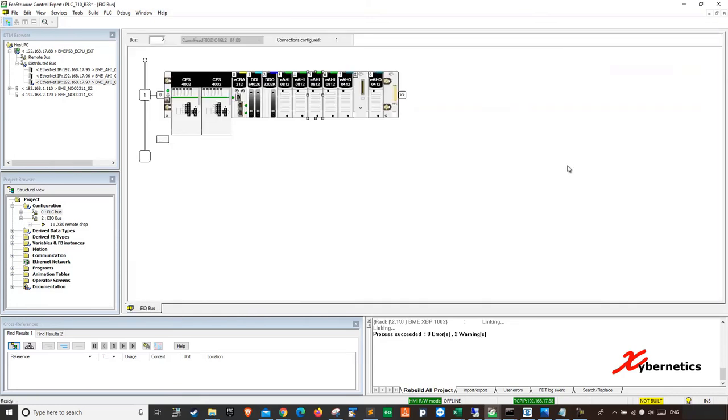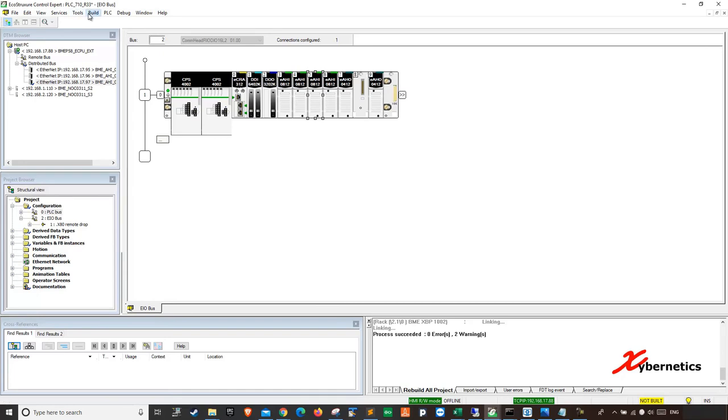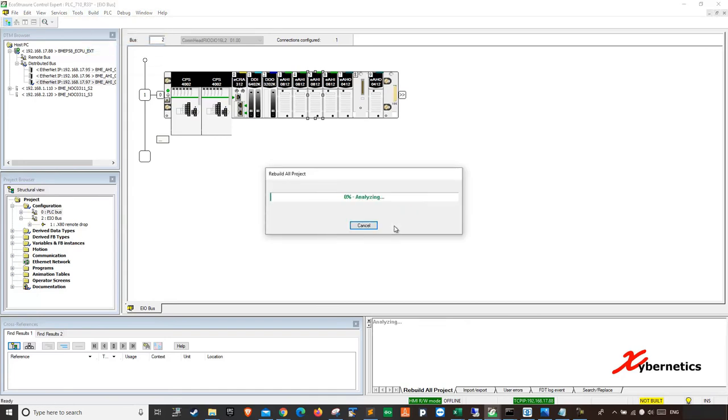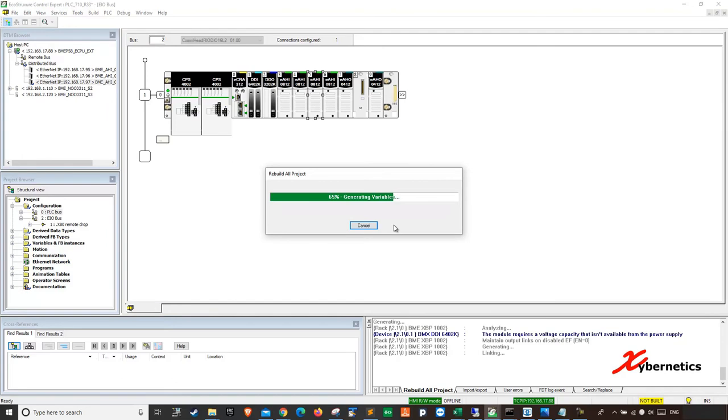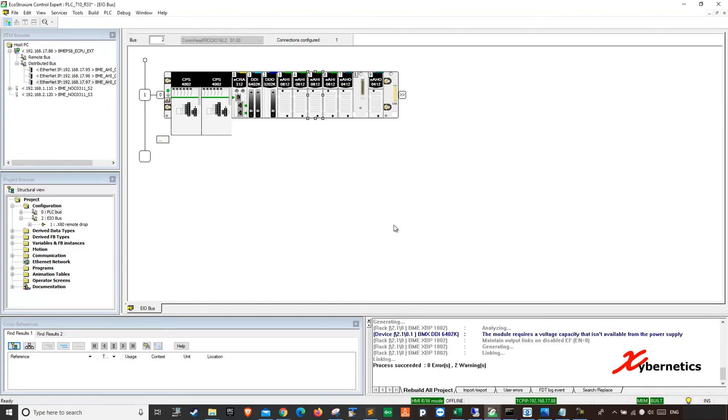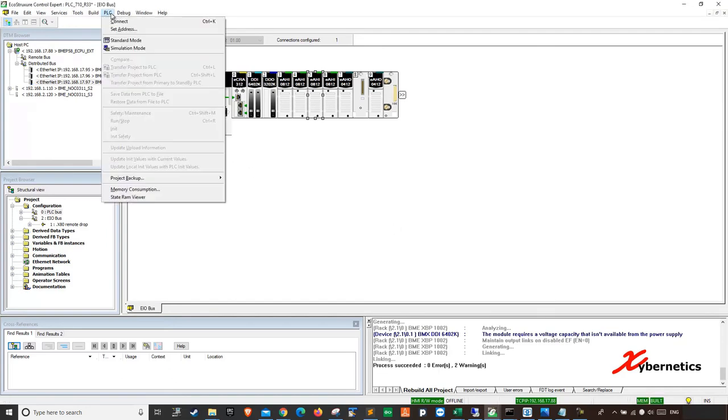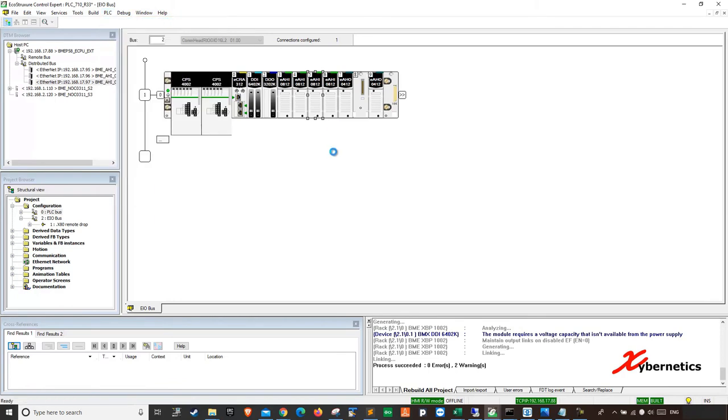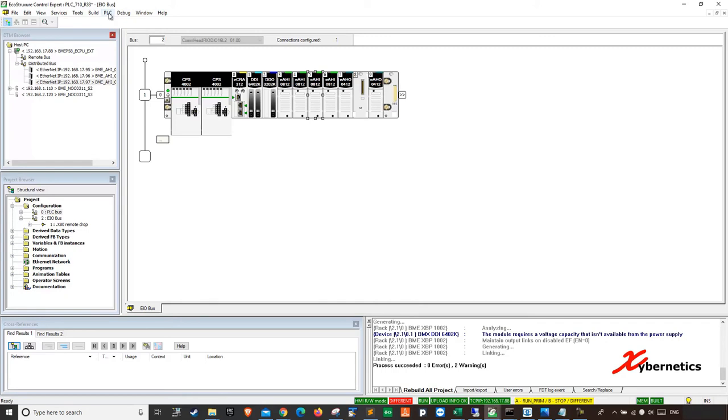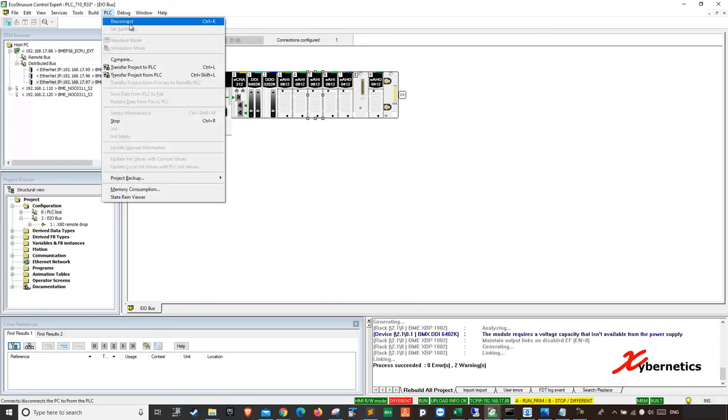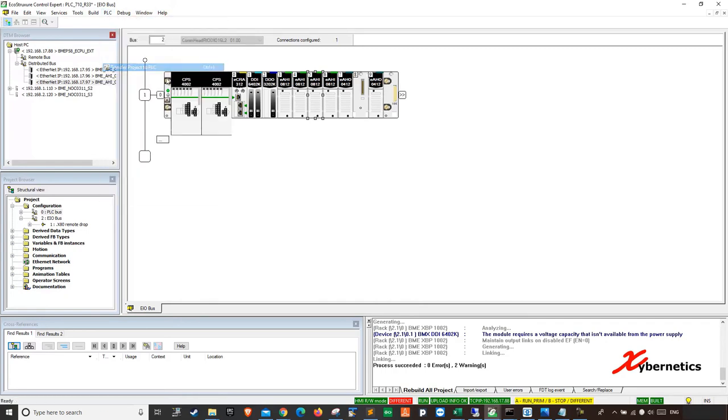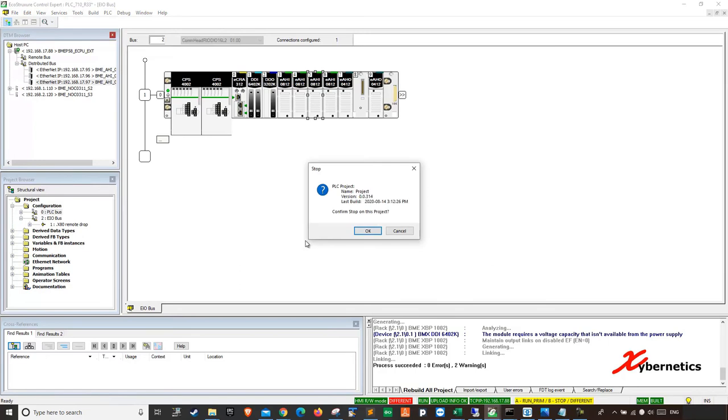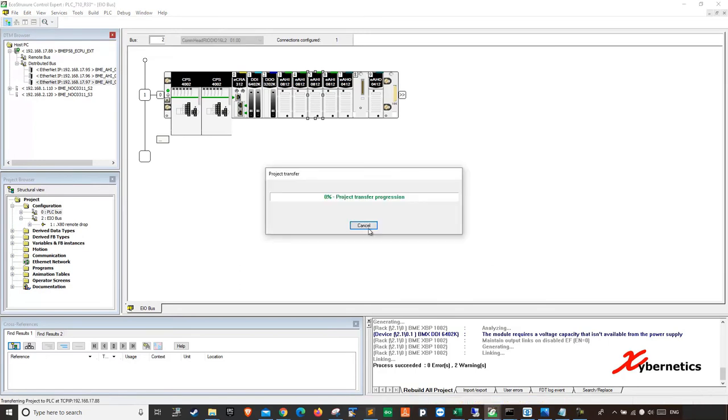So what you have done is you have assigned an identifier and you have disabled the HART because it's going to be 4 to 20 milliamps. So you close this once you're done. So now you're ready to upload the configuration. So you go first, you have to build, rebuild all projects. Once the rebuilding is done, you connect to your PLC back again by clicking connect here.